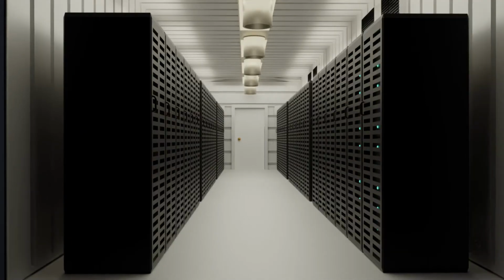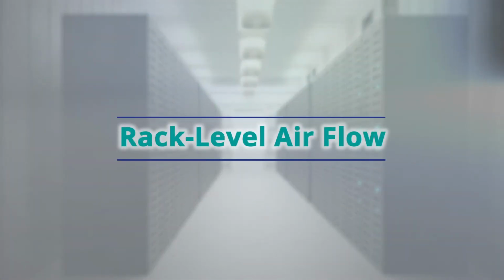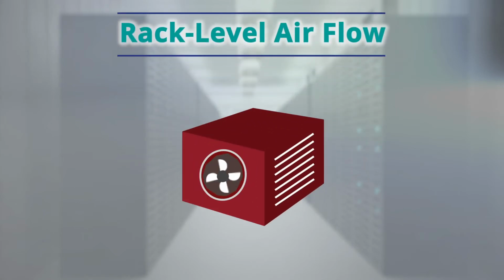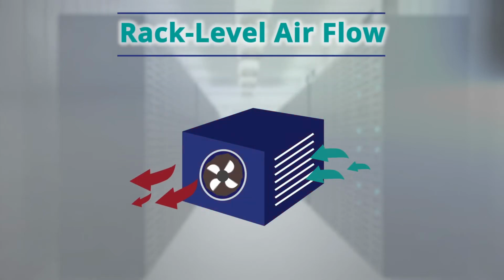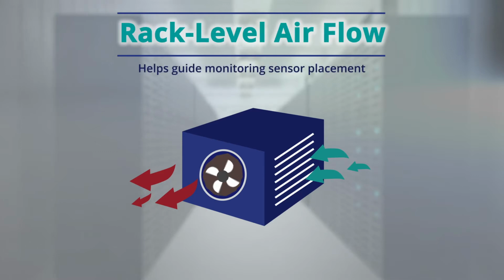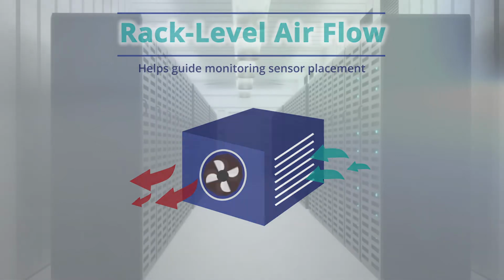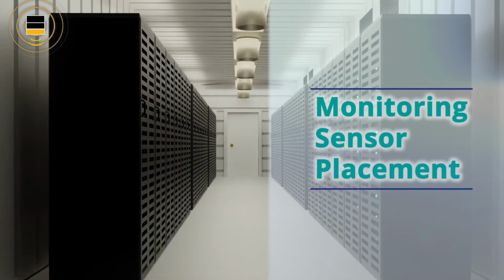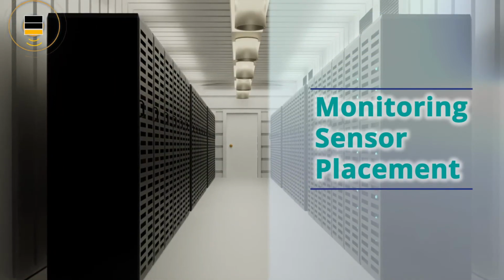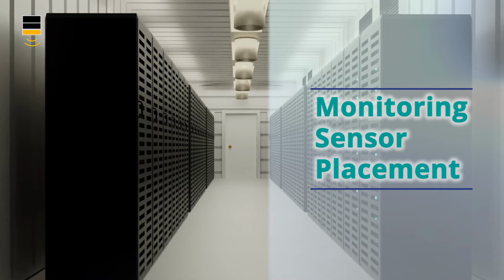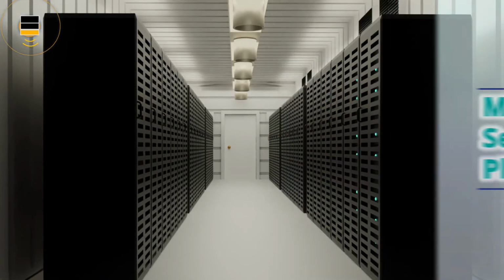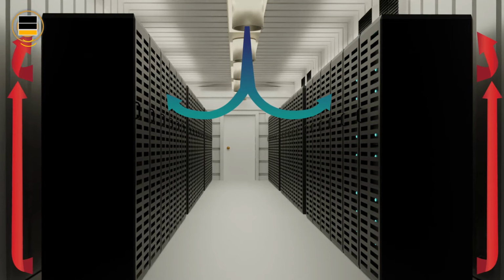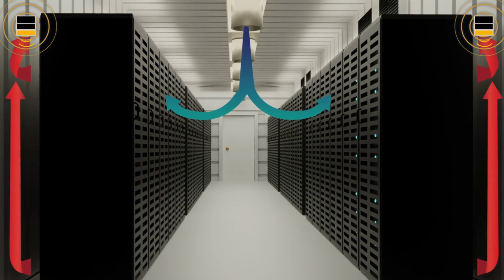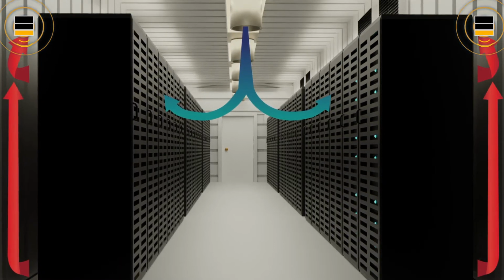Once we know the battery rack design, we want to consider how air flows through the modules and rack. For example, module fans may cool and ventilate the batteries. Fans create this rack-level airflow, which helps guide and optimize monitoring sensor placement. While monitoring sensor placement is based on rack-level airflow, it is not required for sensor operation. However, airflow patterns should be taken into consideration when positioning sensors on or near battery racks.